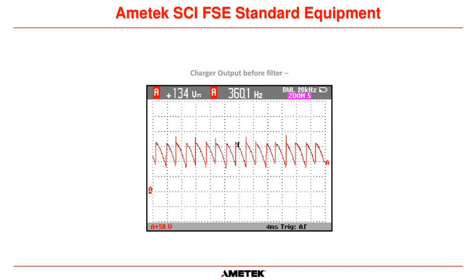So somebody's asked, while I'm talking about SCRs, what is the life cycle of the SCRs? From the manufacturers, they say there is no degradation over time. So remember, we always base our maintenance on what the individual manufacturer of that part says. The manufacturer does not recommend that that part is replaced at any time interval. So therefore, we do not recommend that the SCRs or the transistors are replaced at any point. We only recommend they are replaced after they fail. Okay, so that's a good question. Thank you for asking that.